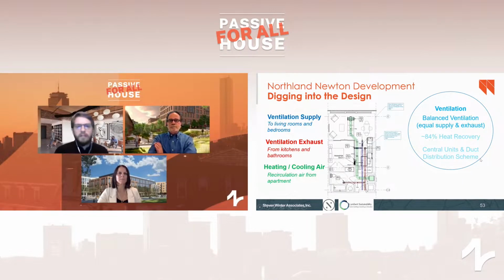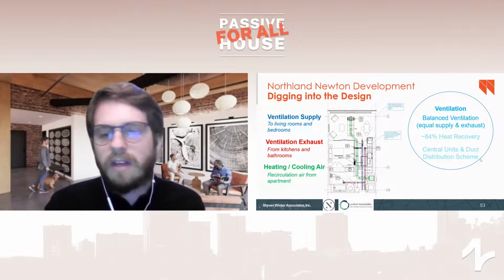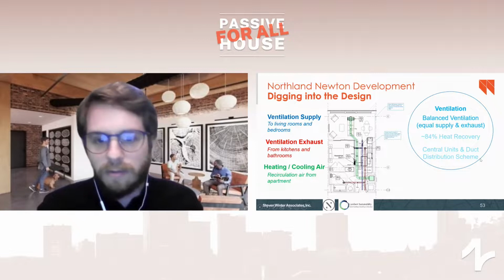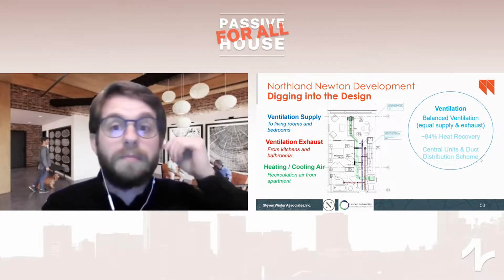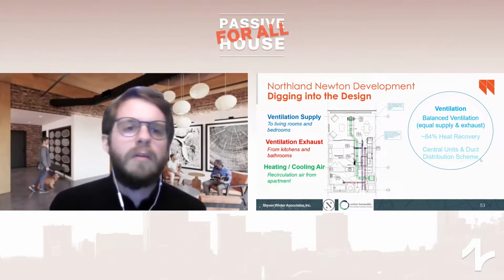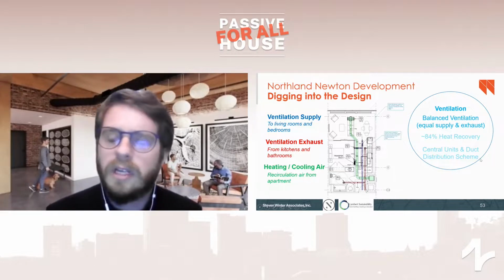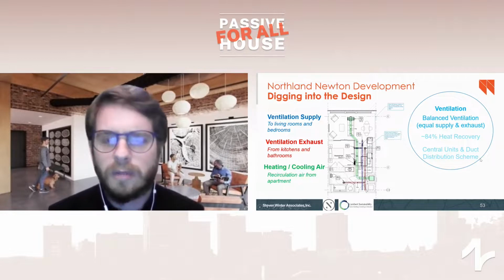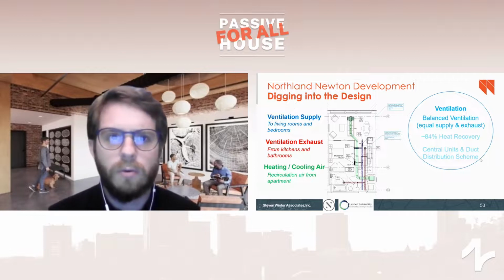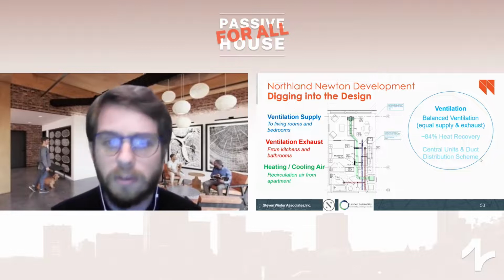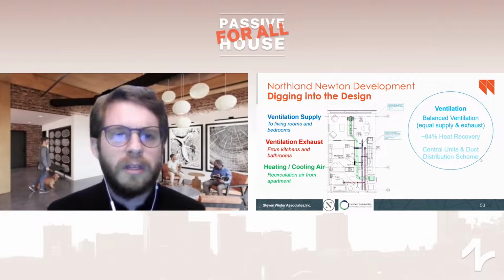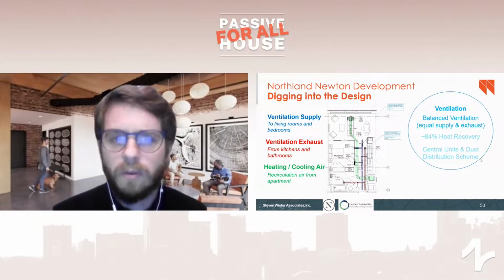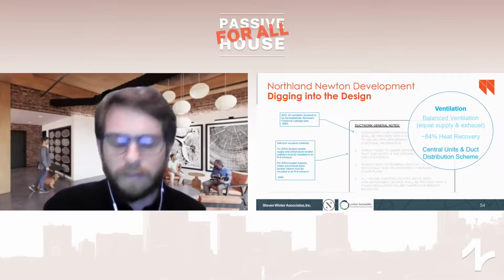Okay, so just a couple of other aspects of the design here. The ventilation system is a centralized ventilation system. And this was to really help limit the number of ERVs in the project, and helps with quality control purposes. It allows you to have your maintenance staff maintain only a couple of ERVs, change filters a couple times a year on a few ERVs, not do it on hundreds of them. And it's balanced ventilation, very typical for passive house, with 84% heat recovery in those units, and central ductwork, which we'll get into in a minute with respect to the measures that are being taken to ensure that the ductwork is sealed properly and working as it should. And then on the heating and cooling side, it's a VRF system with heat recovery, which we'll talk about in a minute, highlighting the benefits of that.